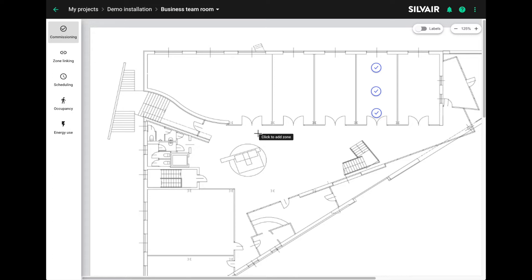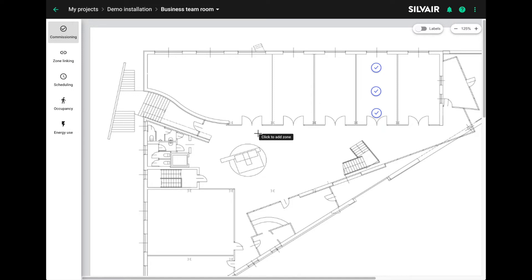However, you do have to assign an energy profile for each zone. Otherwise, we won't be able to calculate the energy usage. Remember that this feature works most accurately if there is only one fixture type in a zone. If you have more than one type of fixture in a room, it's best to put them in separate zones and then use zone linking to link them together. That's how you get the most accurate results.